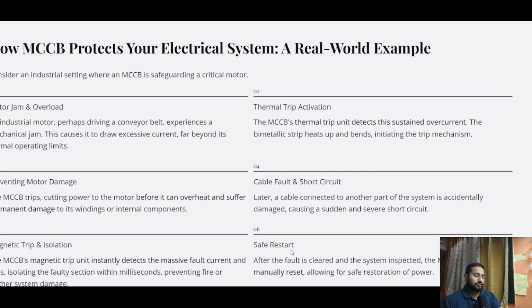So this was about the principle of operation. It has two protections, that is thermal protection and short circuit protection. So we will see how MCCB protects our electrical system, a real world example. Consider an industrial setting where the MCCB is safeguarding a critical motor. The motor is jammed and overloaded. In this case, an industrial motor, perhaps driving a conveyor belt, experiences a mechanical jam. This causes it to draw excessive current far beyond its normal operating limits.